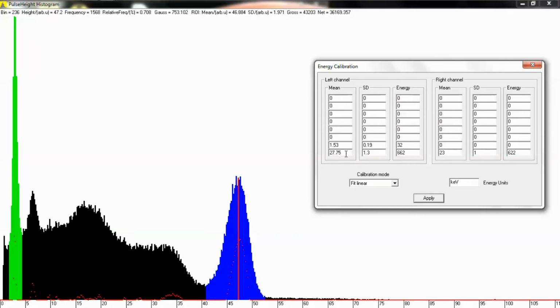Okay, first we need to know what's the mean. The mean, in arbitrary units, is 46.885. All right. And what's the standard deviation from the norm? It should be 1.95 is about right. It's changing a little bit, but it's pretty close to 1.95, right? It goes up, it goes down, it goes up, it goes down. And the energy, we're going to stick with 662. It's actually 661.66, but that's pretty close.